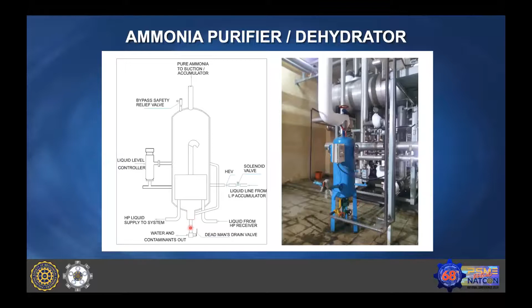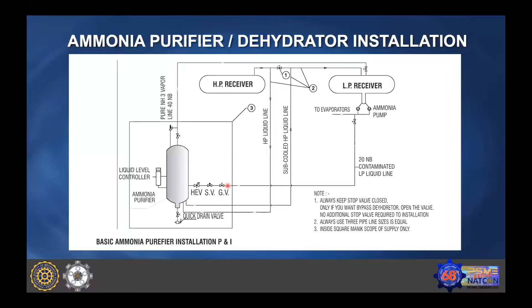If there is water, it gets accumulated at the bottom of this ammonia dehydrator. Normally when it is filled with ammonia, there will be frosting on this dehydrator. When water starts accumulating in the dehydrator, the frosting will go. So when there is no frosting on the lower side, you can drain the water from it. This is a typical installation drawing for the ammonia system, showing how to connect into the running system. This keeps the ammonia purified continuously online, and you don't have to stop the plant to purify the ammonia, which saves a lot of energy in plant operations.